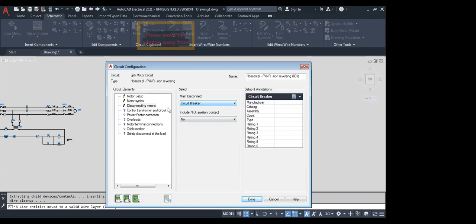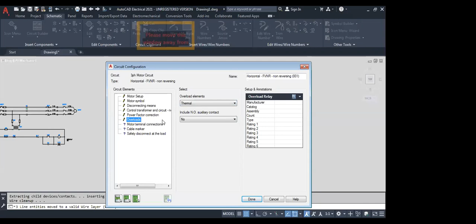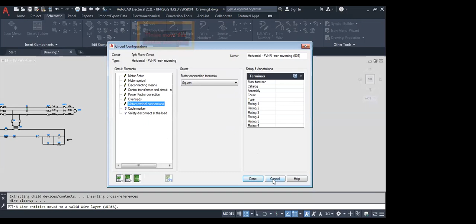Then the control transformer, which transformer we are using — if you're not using a transformer, you can simply click that. Power factor correction: if it's an induction motor, it will consume something related to power factor, so if any power factor correction method is used, we can have that data too. Overload protection classes can also be set here for the motor terminal. All the motor nameplate details used while designing the panel, the MCC panel, can be entered as input in this section.